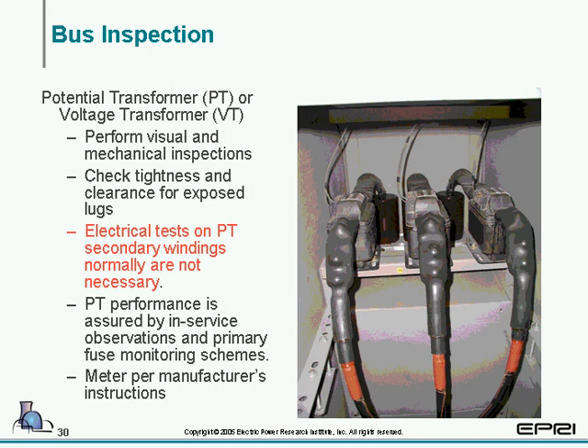After we look at the bus and the insulation, we'll take a look at the PTs, or potential transformers, and the VTs, or voltage transformers. You're going to perform a visual inspection to check for tightness of the hardware. When you're looking at PTs, the performance can be seen in service by looking at the meters and verifying that they are accurate.